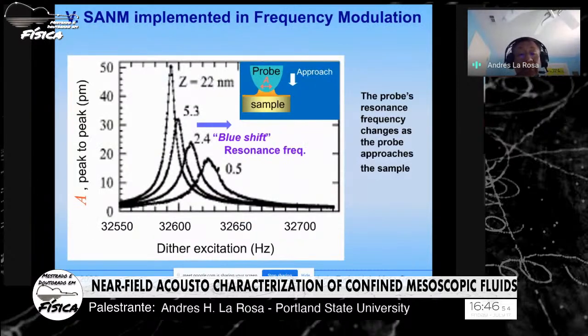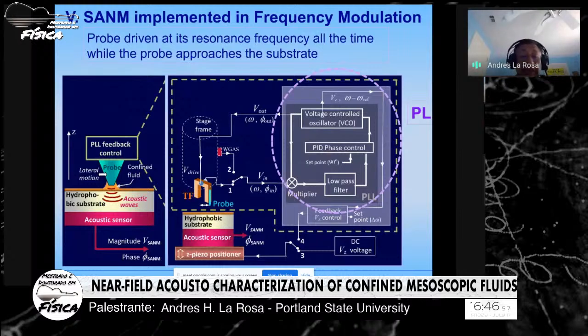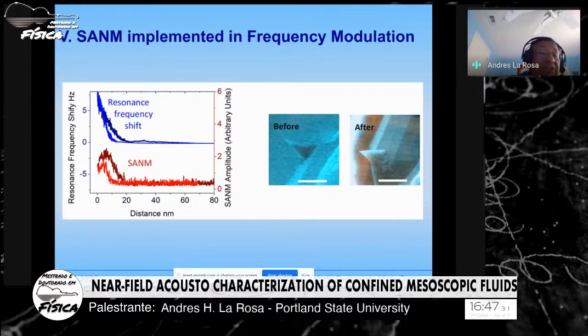Based on the recent results, what we have found is that we incorporated frequency modulation into our microscope. Remember, the resonant frequency of this guy changes when the probe approaches the surface. So we use a phase-locked loop, which is frequency modulation, and it allows you to drive this probe at the instantaneous resonance frequency. In other words, if the resonance frequency increases, you drive it at the new resonance frequency. With that approach, we are able to monitor the change in resonance frequency together with the acoustic one.